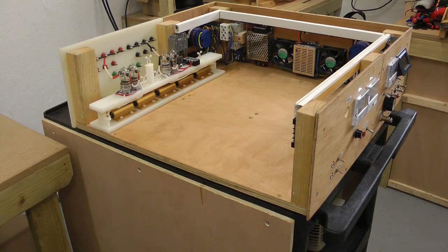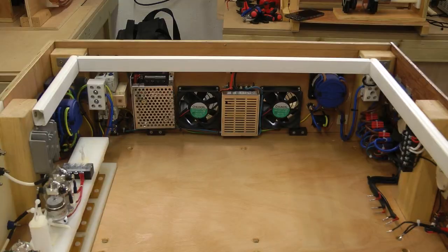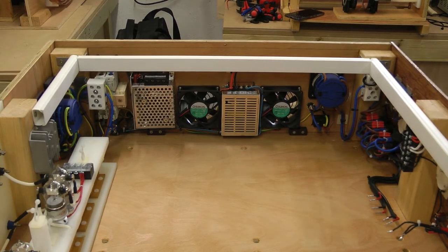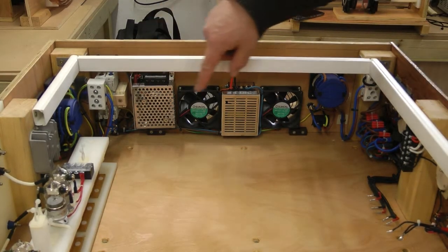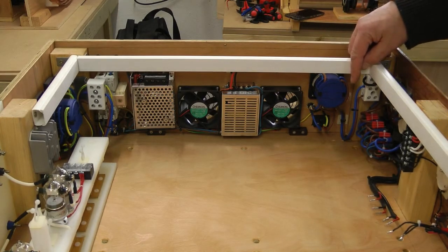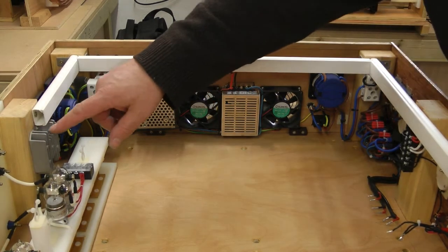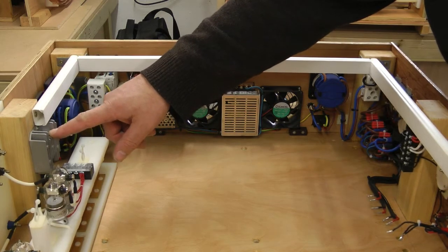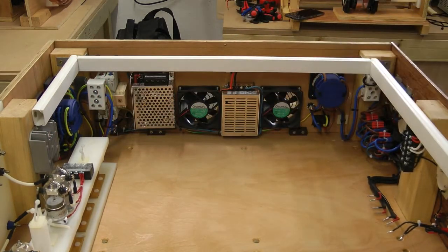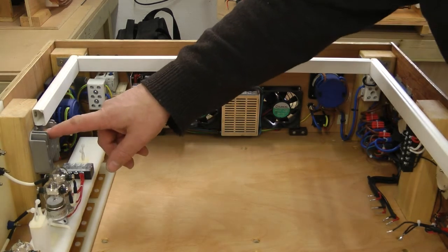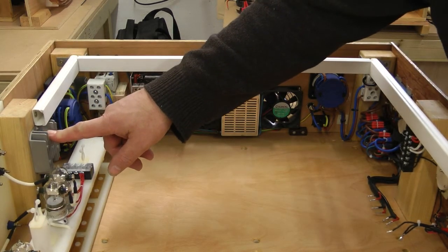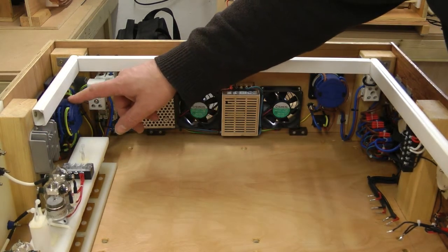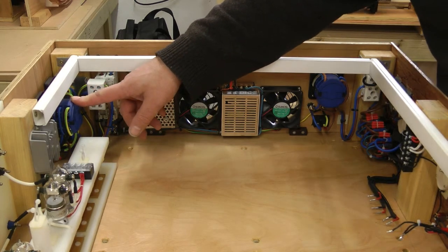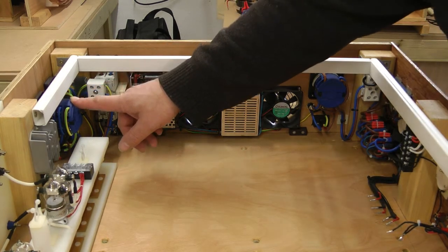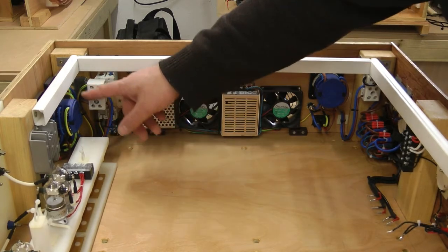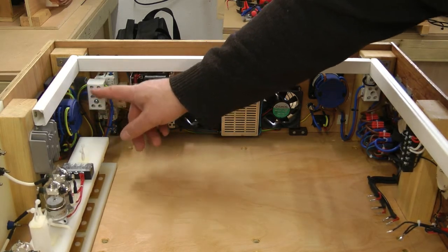So just moving the camera in and just looking at the power control side, so that's everything down this side of the plate supply. As I said before, there's a 24 volt module that runs off of the 15 volts and gives 24 volt out to DC to DC converter. There is the 3-pole switch here to switch the external power meter. Obviously power coming in from the rear panel.